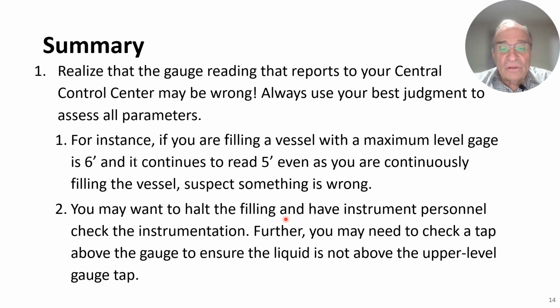You may want to halt the filling and have an instrument person check out the instrumentation. Further, you may need to check a tap above the gauge to ensure that the liquid is not above the upper gauge level. That would typically be done by your outside operator.